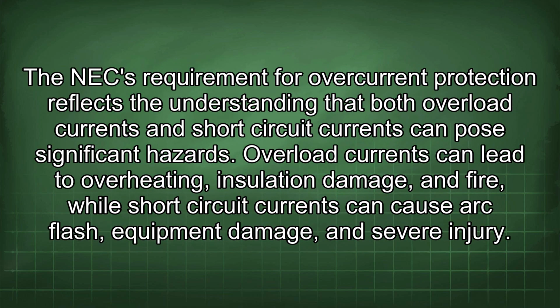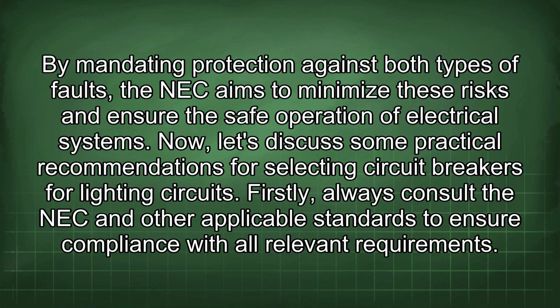The NEC requirement for overcurrent protection reflects the understanding that both overload currents and short-circuit currents can pose significant hazards. Overload currents can lead to overheating, insulation damage, and fire, while short-circuit currents can cause arc flash, equipment damage, and severe injury. By mandating protection against both types of faults, the NEC aims to minimize these risks and ensure the safe operation of electrical systems.